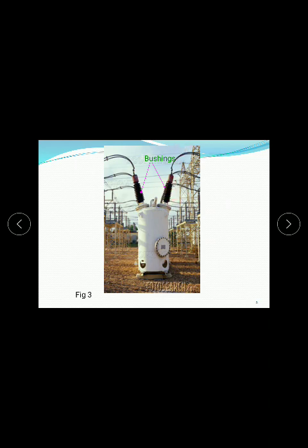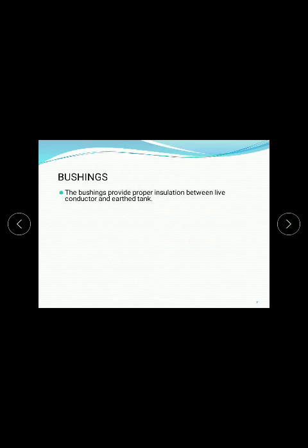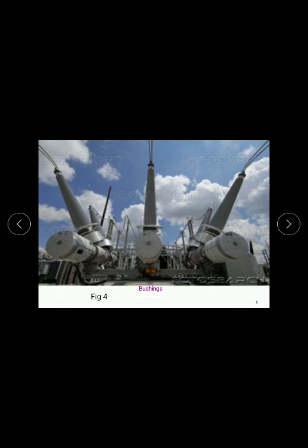These are the terminals and these are the bushings - just like an insulator. The bushings provide proper insulation between the live conductor and the earthed tank. The bushings are made of a porcelain cylinder which will have more dielectric strength. The bushings are positioned between the conductors and the tank.